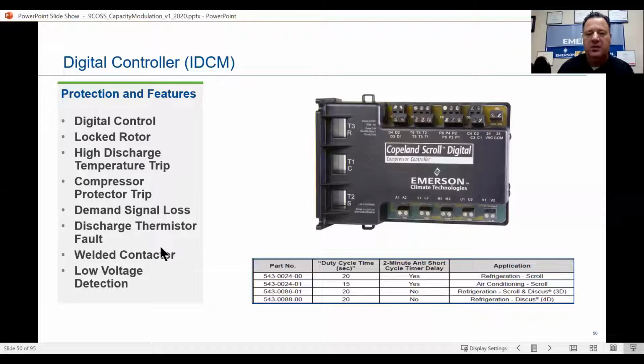So if that welded contactor gets welded on one of the phases, instead of it burning up the compressor, what it does is it calls for it to come back on. That's how the protection is developed on the welded contactor. All right, so it comes back on, it sets off an alarm, whether that be a strobe, a sound, going to your E2 or whatever the controller is.